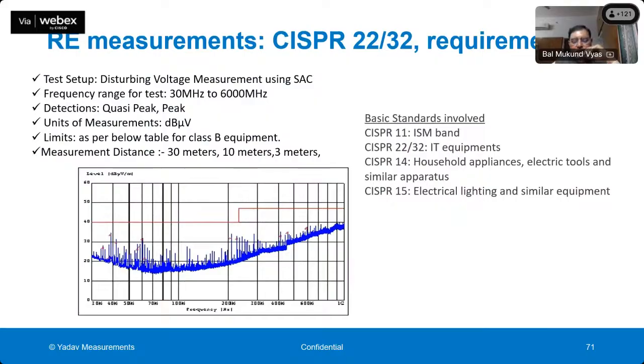Again, this is a very expensive test because you can test only one meter at a time. You have to rotate the meter through 360 degrees at different small angles and find out where the peak emission is. And then once you identify the peak, you have to test for quasi-peak and average radio frequency. So that is why this takes a lot of time.